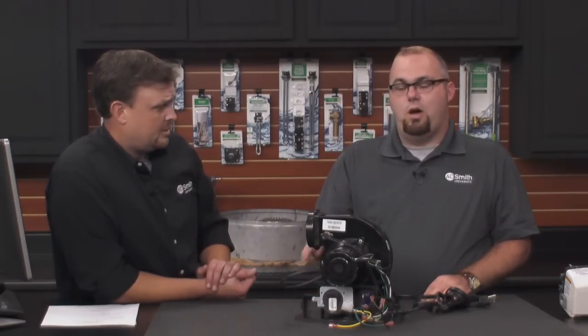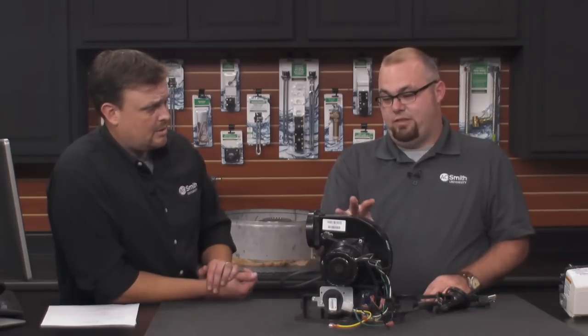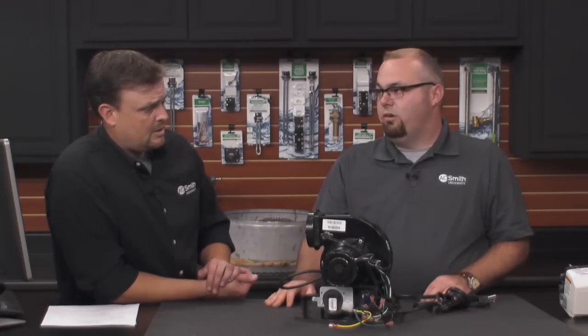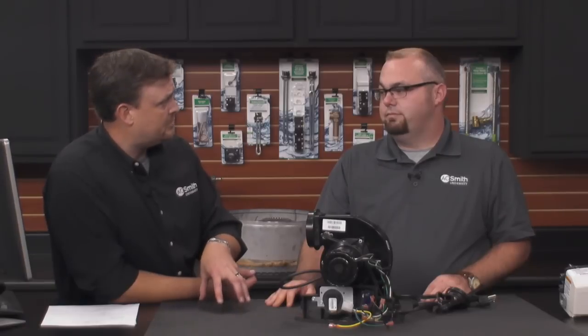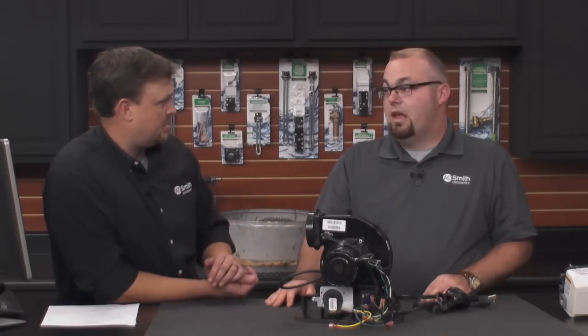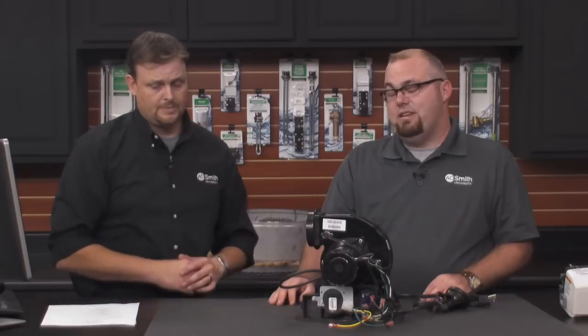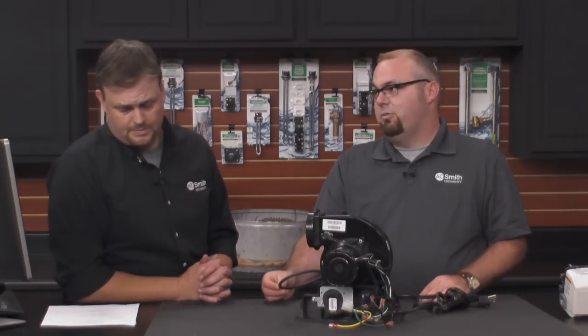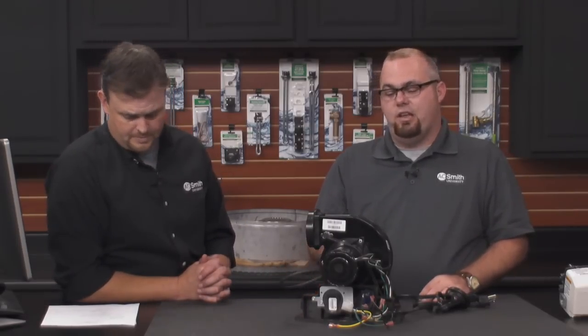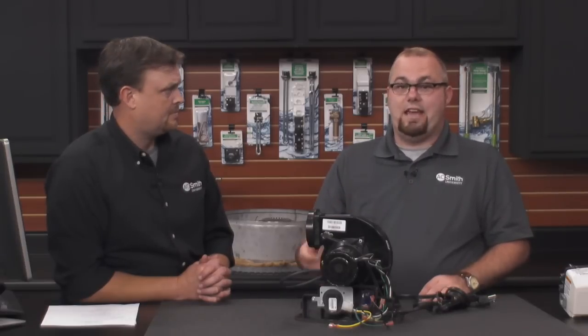Yeah, on typical models like this one, it's 100. That this blower would come off of it, it's 145 degrees. Yeah, because we have to keep those flue temperatures low because we're using PVC, correct? Yeah, we are using PVC, and PVC, it's plastic pipe, it can only handle so much heat. So it's a safety device to ensure that we don't cause any damage to the venting.